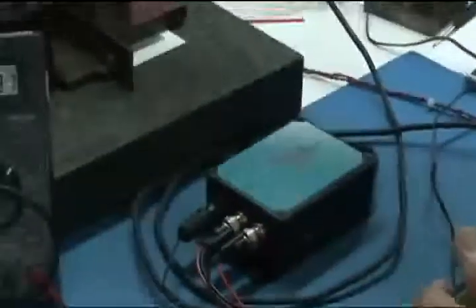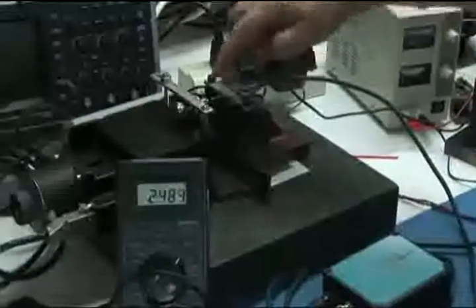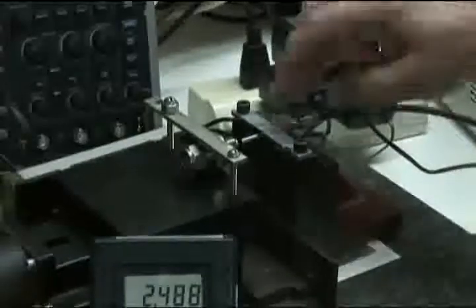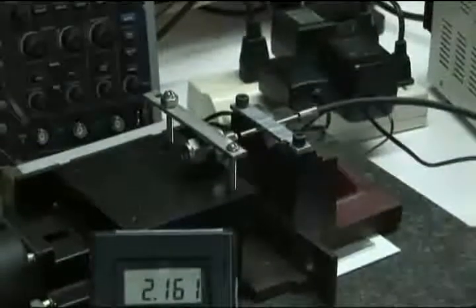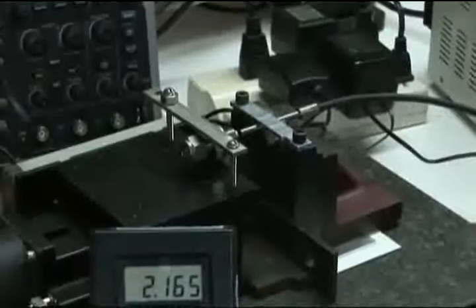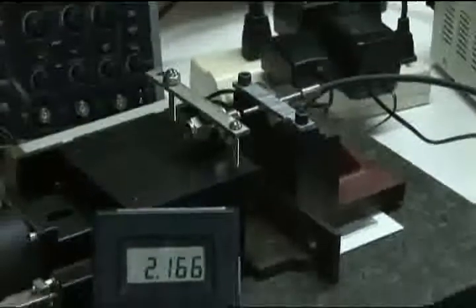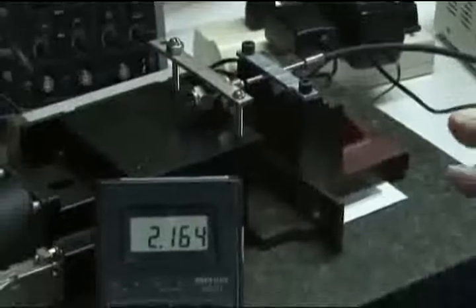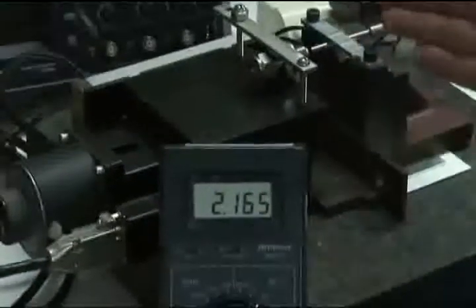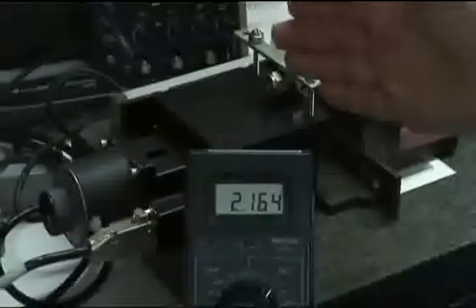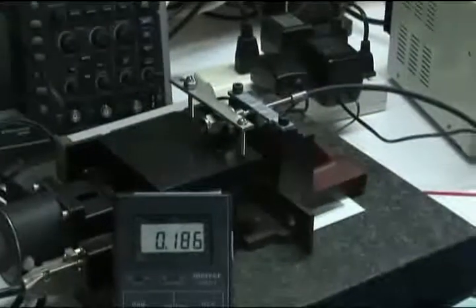Now, on a linear ball bearing stage here, we have your target pin, which is mounted in a compression fitting and clamped, and it's mounted perpendicular to the axis of motion. We have the sensor tip, again mounted perpendicular to the face of your target, and I'm going to run through a calibration first. The way we run through a calibration, we have a control program that's going to bring the stage into contact with the target and then pull it away in steps.